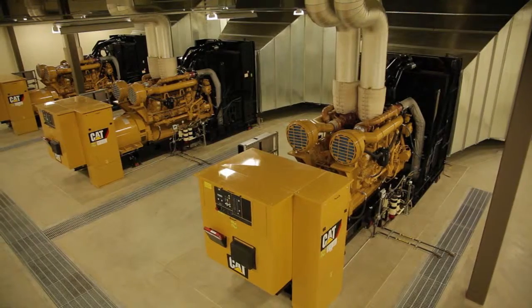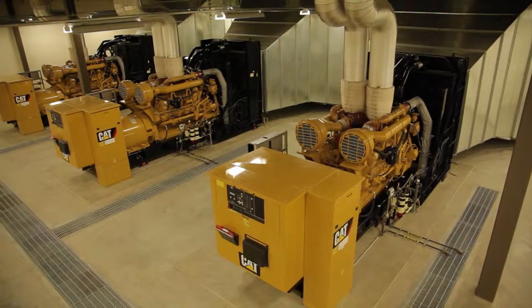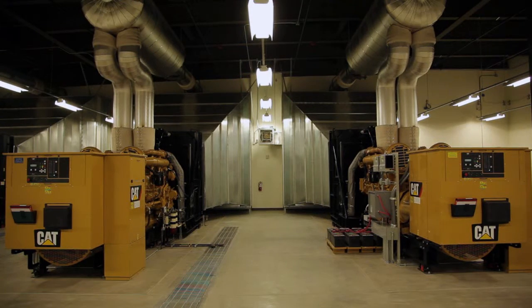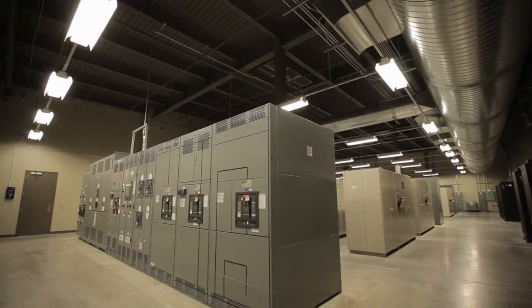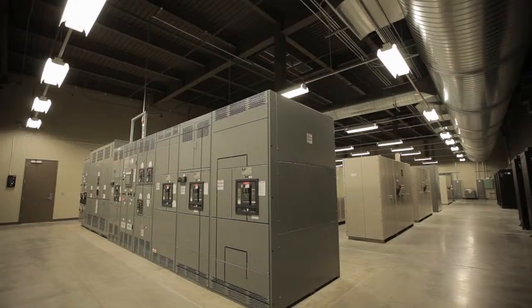The other thing that this design has allowed us to do, when we were looking at it, we were able to reduce the size of our generators. So we didn't have to install as much mechanical refrigeration as we do in our typical data center. So instead of installing 2 megawatt generators per our original plan, we were able to downsize those to 1.5 megawatt generators. And that means we were able to downsize switchgear. It means we were able to downsize copper feeders. So we were able to save copper and save capital costs on our electrical installation that helped in the overall build of the data center.